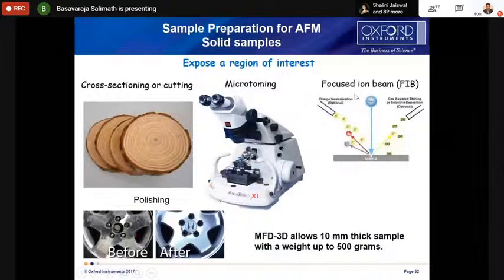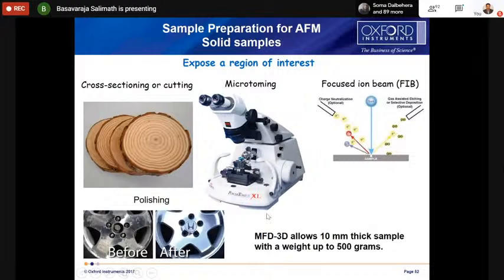Okay, and now coming to how to prepare the sample. As I told, our AFM can take samples up to 10 mm thick. If your sample is a solid sample within 10 mm thickness, then you can keep the sample directly. But if your sample is very big, you need to do cross sectioning or cutting or microtoming, or you can use the FIB. And also, as I mentioned earlier, it can measure surface heights of a maximum of only 10 micrometers, not more than that. So if your sample is too rough, you may need to polish it, and then do the imaging in the AFM.